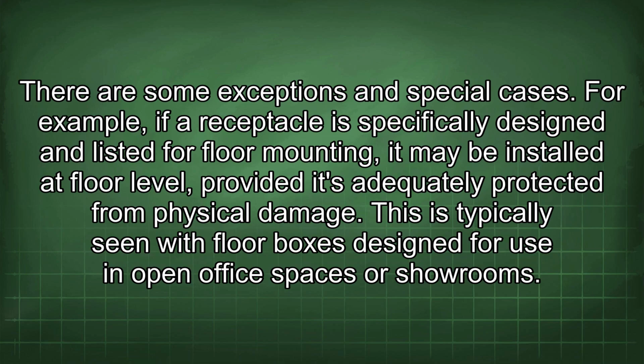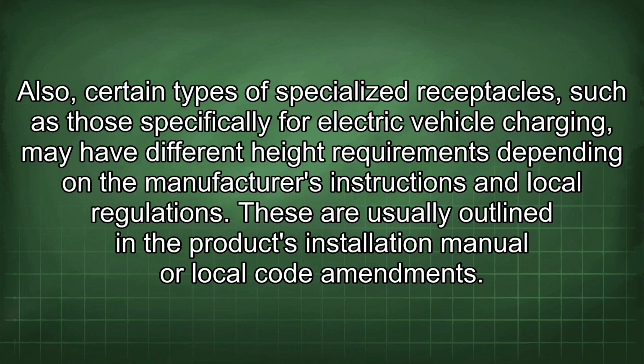There are some exceptions in special cases. For example, if a receptacle is specifically designed and listed for floor mounting, it may be installed at floor level, provided it's adequately protected from physical damage. This is typically seen with floor boxes designed for use in open office spaces or showrooms. Also, certain types of specialized receptacles, such as those specifically for electric vehicle charging, may have different height requirements depending on the manufacturer's instructions and local regulations. These are usually outlined in the product's installation manual or local code amendments.